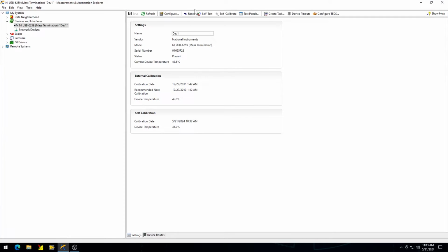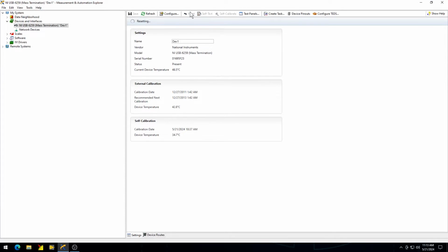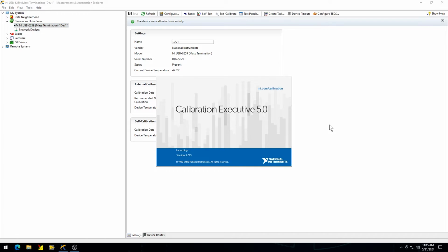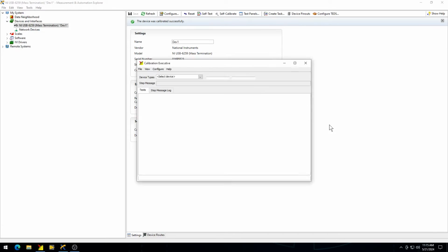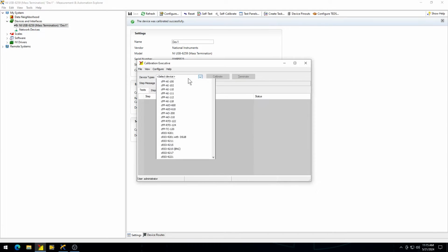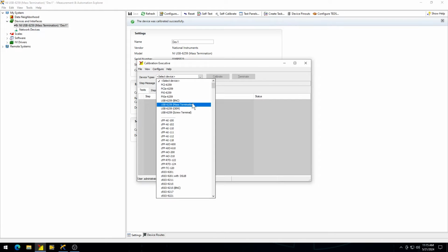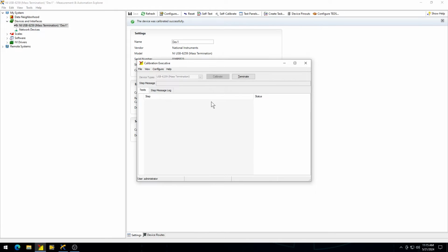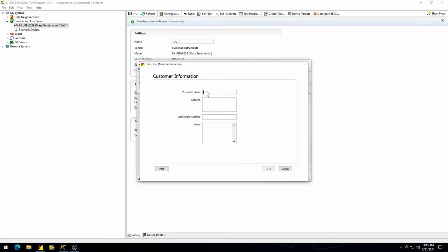Perform basic tests. Click the Self-Test button to perform a basic verification of hardware resources. Then click the Self-Calibration button. Once the device passes both tests, proceed to the next step. Launch Calibration Executive. Open Calibration Executive software. Select your device under Device Types and click Calibrate next to the drop-down menu. Fill out the required forms with your information and proceed.